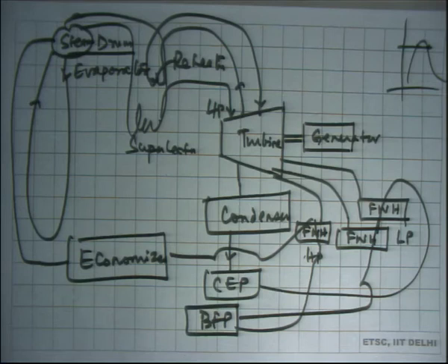In the plant that we saw, these pumps are driven by a dedicated turbine. There is no electric motor in the main pump, but there is an electric motor in the standby pump. In case the turbine driving the boiler feed pump fails or there is some problem with the turbine, you can switch over to the motor driven system, and in the meantime service the turbine. So, that turbine again takes steam from the main steam line. It operates the turbine, which generates something like 7 megawatts, and that is the 7 megawatt input that you require for running the boiler feed pump.